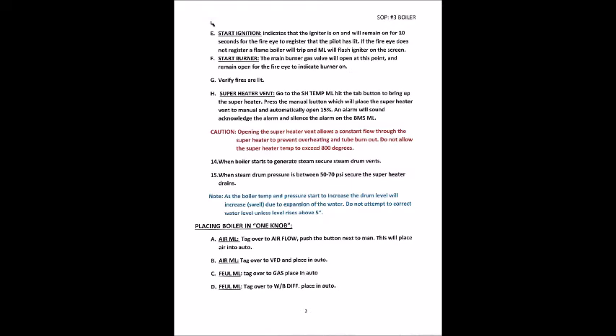F. Start burner. The main burner gas valve will open at this point and remain open for the fire eye to indicate burner on. G. Verify fires are lit. H. Superheater vent. Go to the SH temp ML. Hit the tab button to bring up the superheater. Press the manual button, which will place the superheater vent to manual and automatically open 15%. An alarm will sound. Acknowledge the alarm and silence the alarm on the BMS ML.